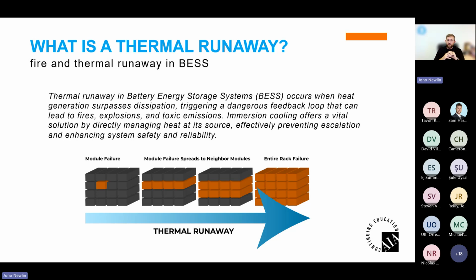So what happens is one cell goes into thermal runaway, which causes the module to propagate to all the touching and neighboring cells. Now this module fails, then you get that spread to module failure, enabling all the modules, and then eventually the entire rack. So again, it's a short circuit triggering inside where it overheats and it just creates this feedback loop.